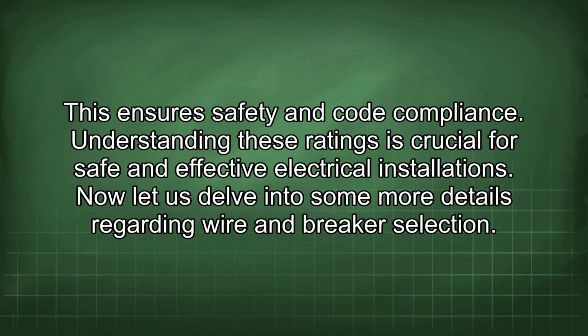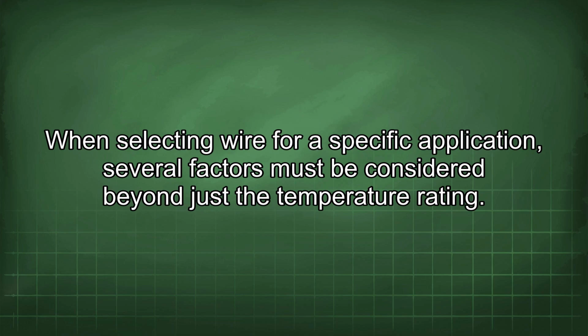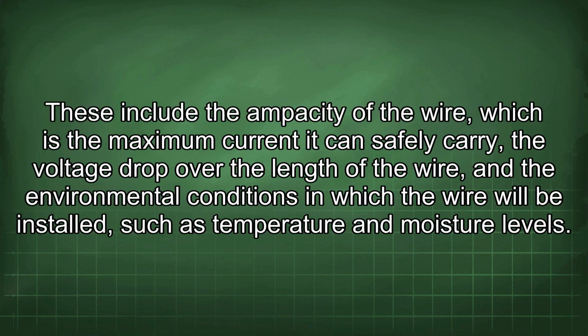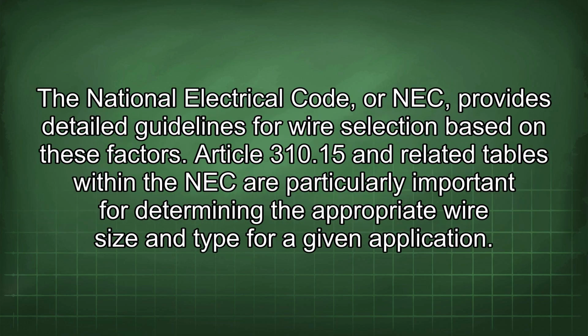Now let us delve into some more details regarding wire and breaker selection. When selecting wire for a specific application, several factors must be considered beyond just the temperature rating. These include the ampacity of the wire, which is the maximum current it can safely carry, the voltage drop over the length of the wire, and the environmental conditions in which the wire will be installed, such as temperature and moisture levels. The National Electrical Code, or NEC, provides detailed guidelines for wire selection based on these factors.